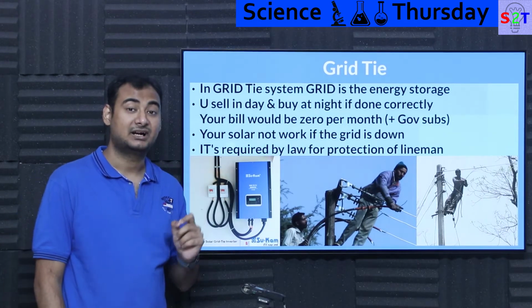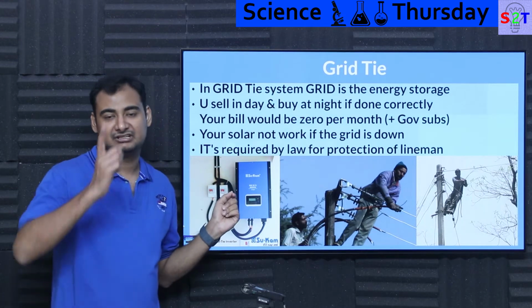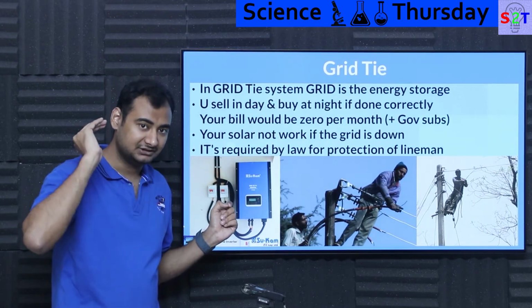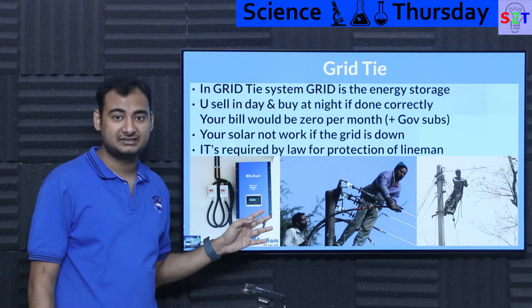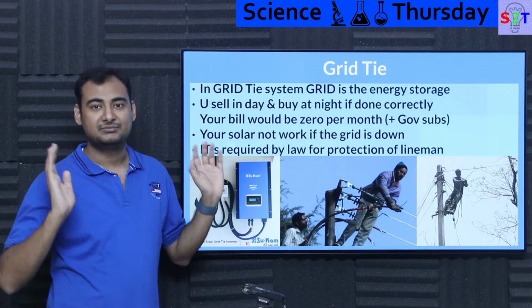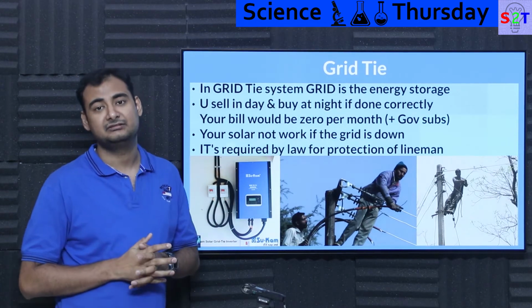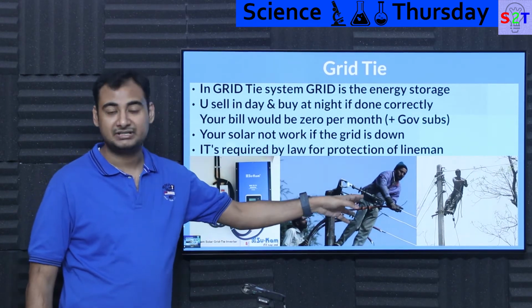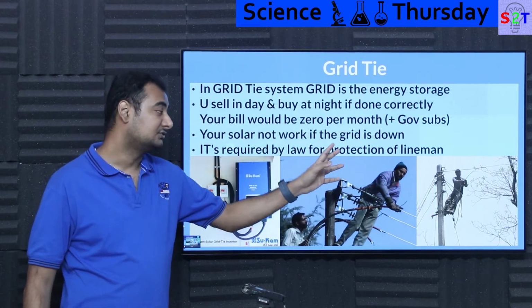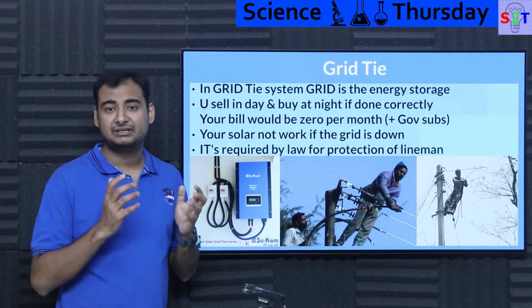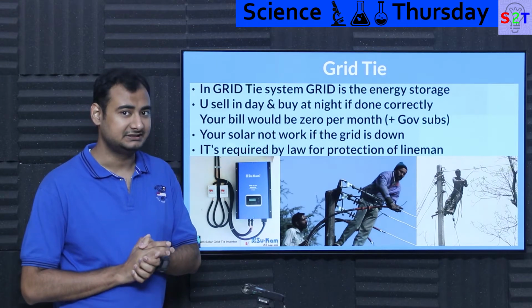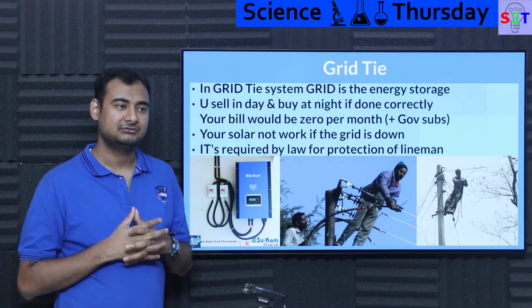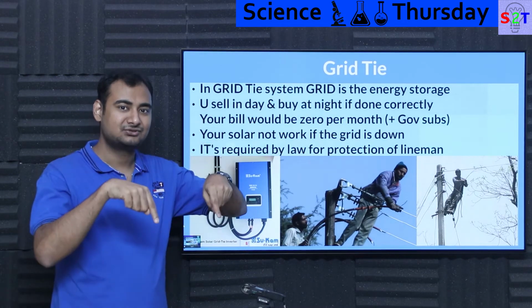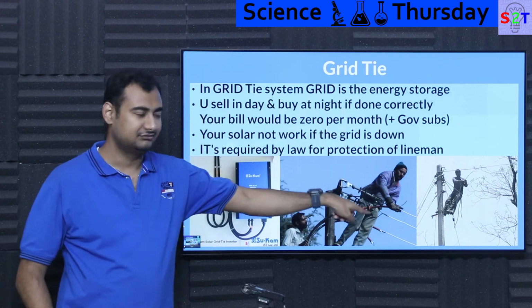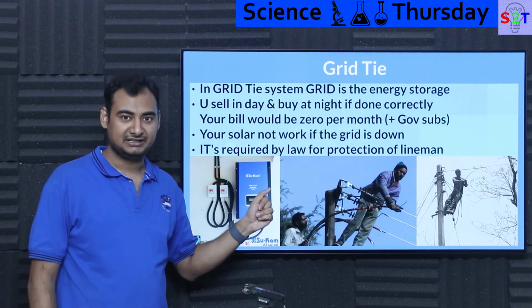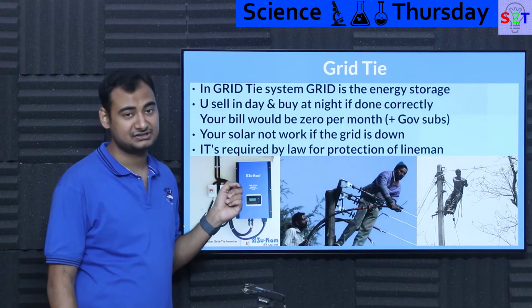The reality is this is required by law: if your inverter has the capability of feeding power back into the grid, it must cut out if it detects the grid is down, because if the grid is down, somebody is likely working on it, or will be shortly. So the assumption is always that someone is working there, and the worker must be protected. Think about 220 volts, that's lethal enough, and electricity has a habit of jumping transformers, so you send 220 volts in and 11 kV can come out on the high voltage side. If a worker is working on that, bye bye the worker. So fundamentally this is a protection system required by law.